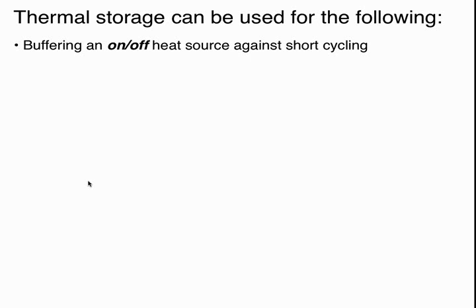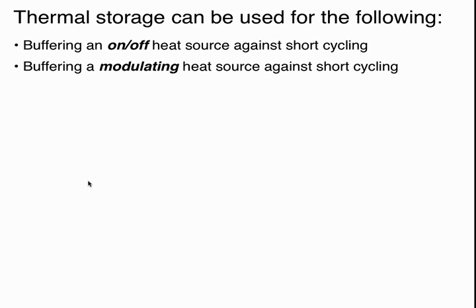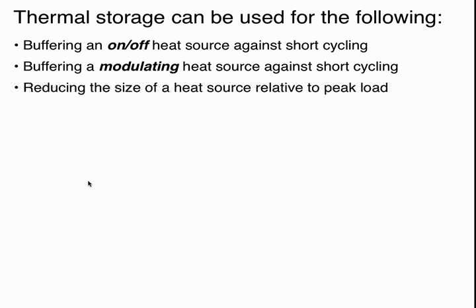And over the course of a heating season, that can be tens of thousands of start-stop cycles. It's going to take its toll on the equipment in that boiler, things like hot surface igniters or contactors in a heat pump. So we want to protect against short cycling, both with on-off boilers and also with modulating boilers.